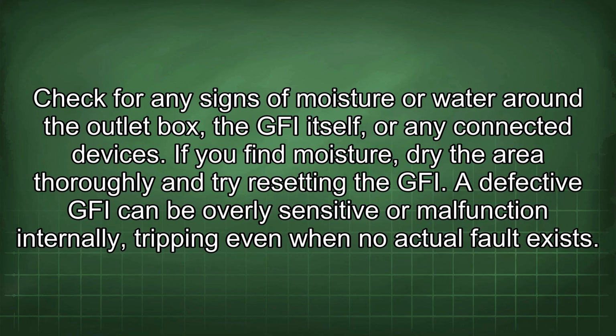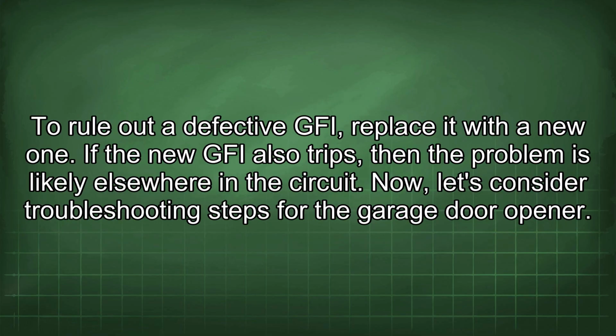Check for any signs of moisture or water around the outlet box, the GFI itself, or any connected devices. If you find moisture, dry the area thoroughly and try resetting the GFI. A defective GFI can be overly sensitive or malfunction internally, tripping even when no actual fault exists. To rule out a defective GFI, replace it with a new one. If the new GFI also trips, then the problem is likely elsewhere in the circuit.